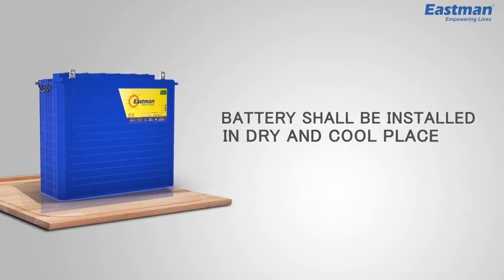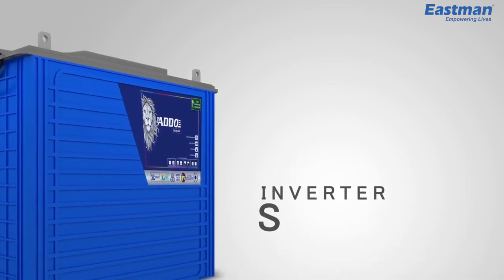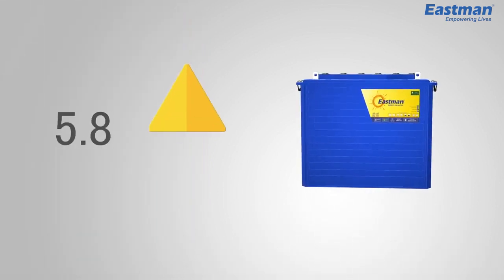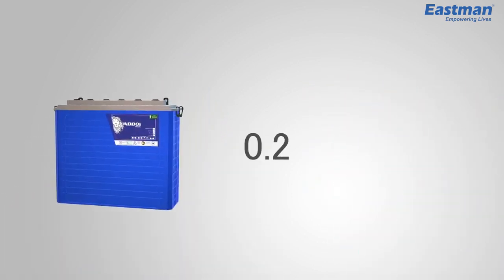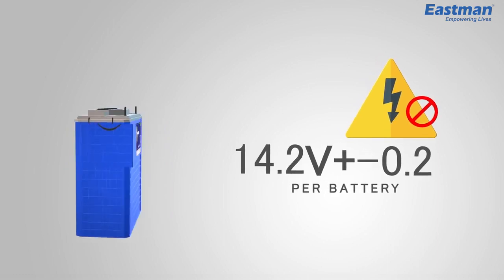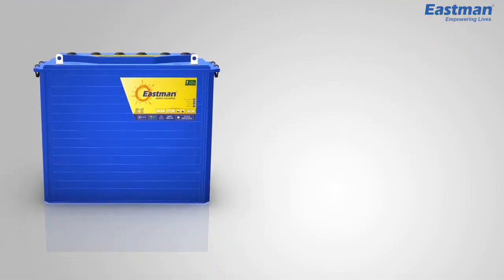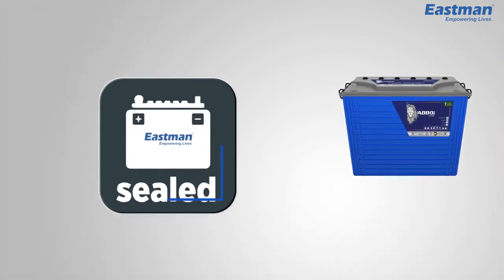Battery shall be installed in a dry and cool place with a well-ventilated area. Always keep the inverter at SMF mode for tubular gel battery when it is in service. Float charge voltage shall not be more than 13.8 volts per battery. Boost voltage shall not be more than 14.2 volts plus or minus 0.2 per battery. Boost charge is not required when it's in float service. Low voltage or discharge voltage cutoff shall be 10.8 volts per battery.